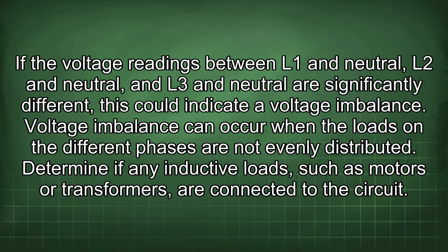If the voltage readings between L1 and neutral, L2 and neutral, and L3 and neutral are significantly different, this could indicate a voltage imbalance. Voltage imbalance can occur when the loads on the different phases are not evenly distributed.